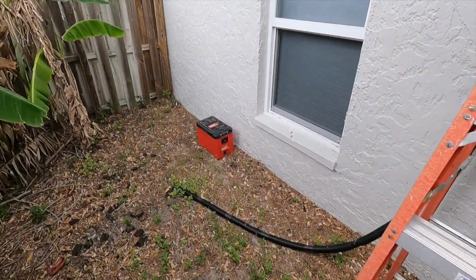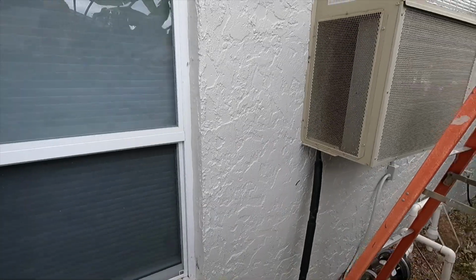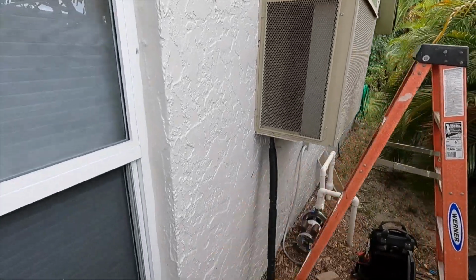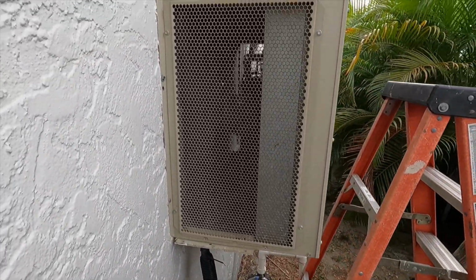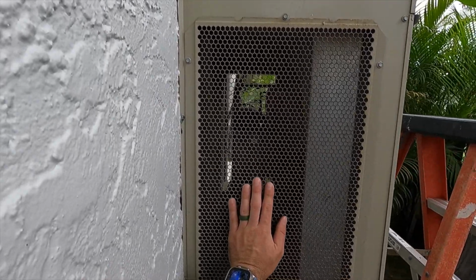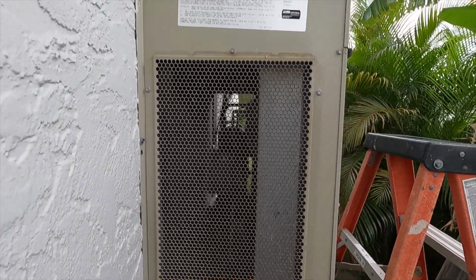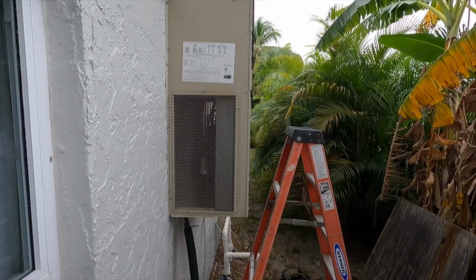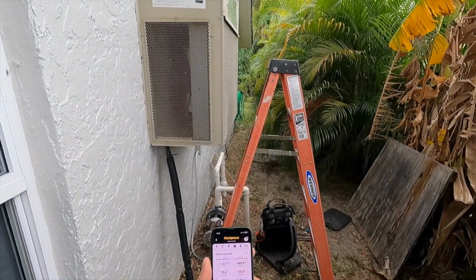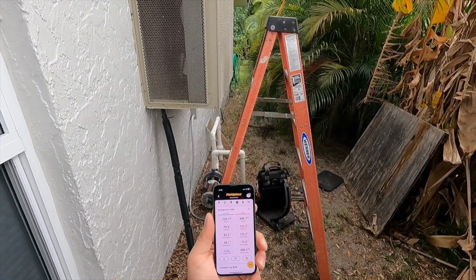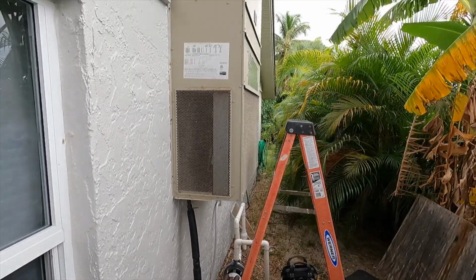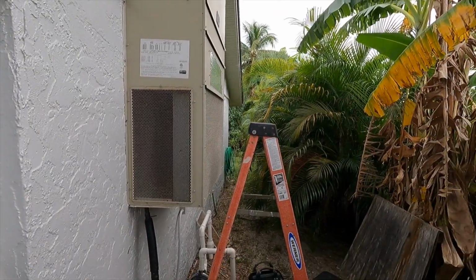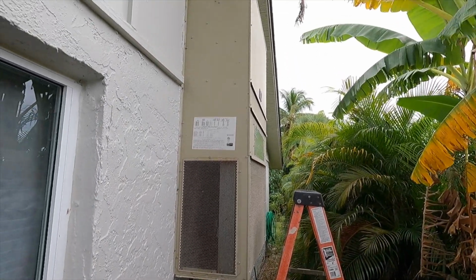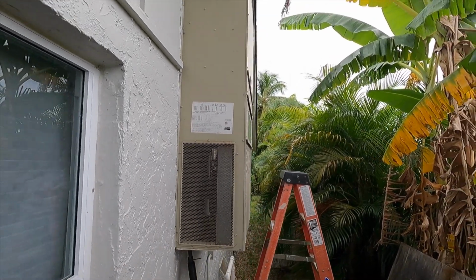So we got an increase in temperature there to begin with, and then we're drawing air through the side here, and it's not a lot. It's not a lot of airflow. So that's quite a bit of a task for a system to reject heat that way, but that's again why we have that high head pressure of 449 psi. I know when they want to replace this thing at some point, we're going to be going with a different setup, more than likely trying to get a split system in there.